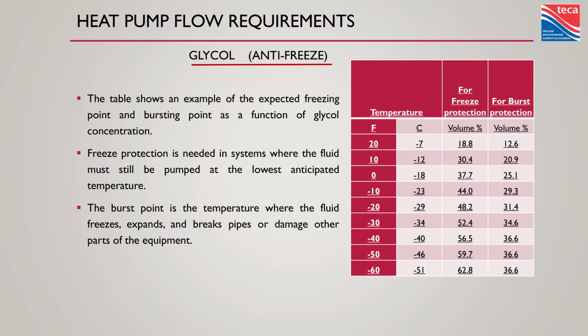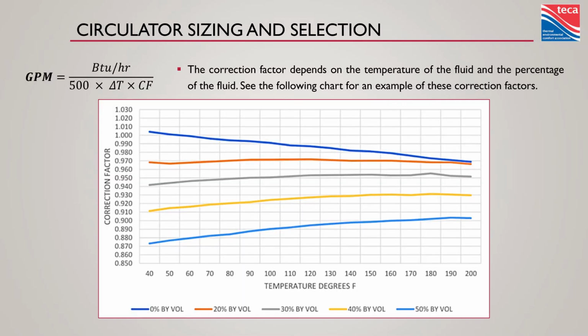Make sure you're protected for the application, but don't just throw as much glycol as you can in there because there's a massive effect on pressure drop and flow rate, as I mentioned before. How much? Well, here's a correction factor slide of flow rates. So roughly at, let's call it 30% glycol by volume, and let's call it 100 degree Fahrenheit water, we now only transfer 95% of the heat at the same flow rate as we would have if it was 100% water. So we're going to need to increase our design flow rate to still get that 100% goal we had. 5% is not a lot.